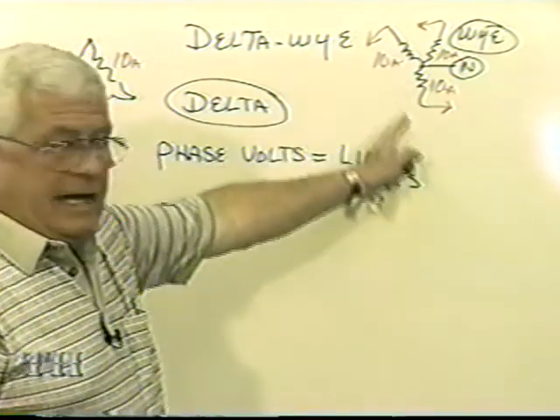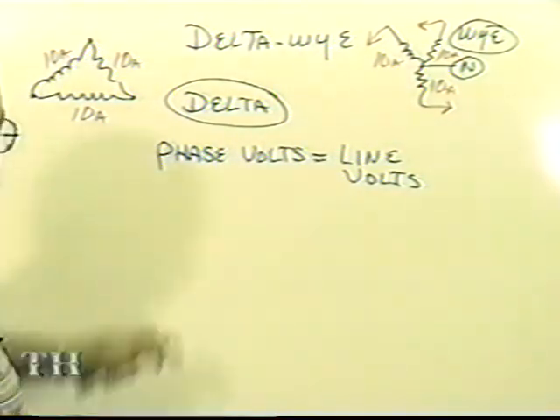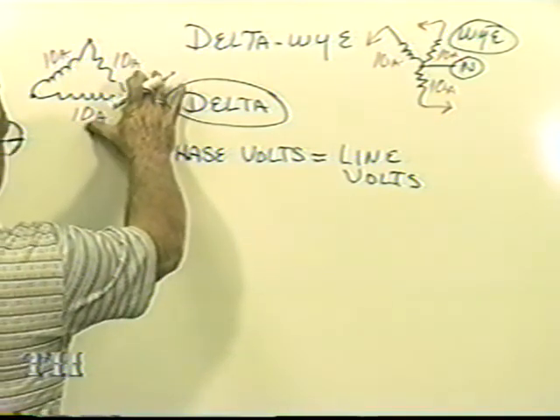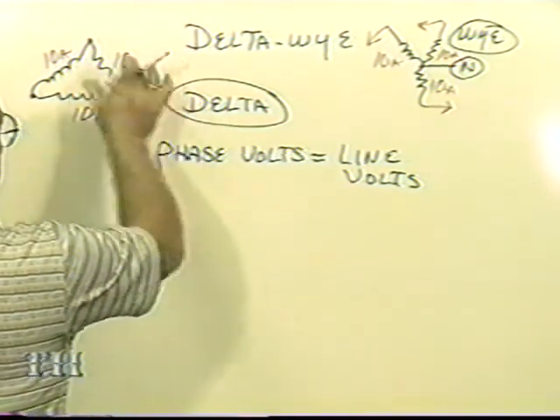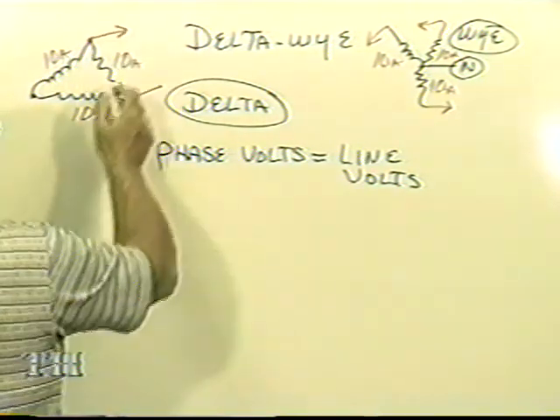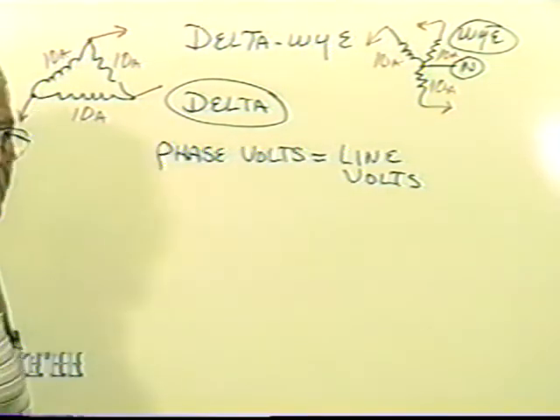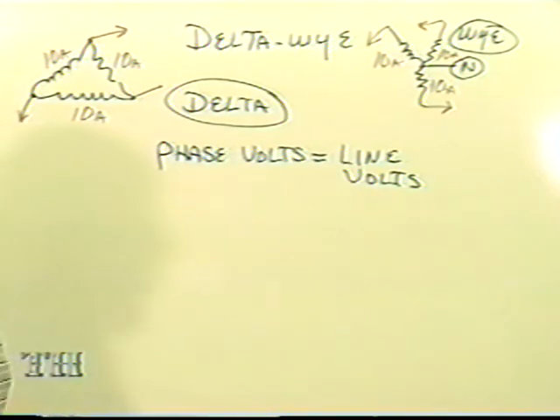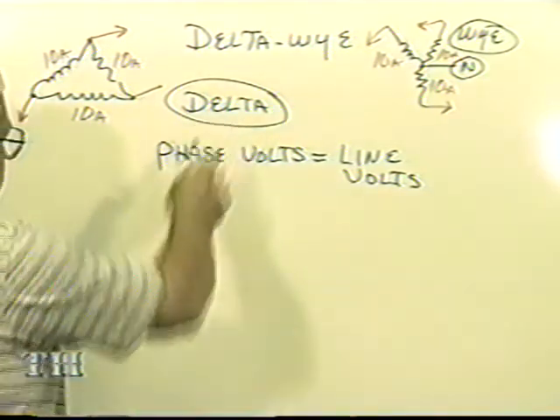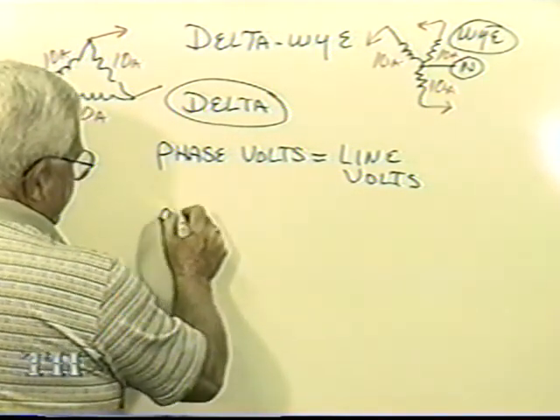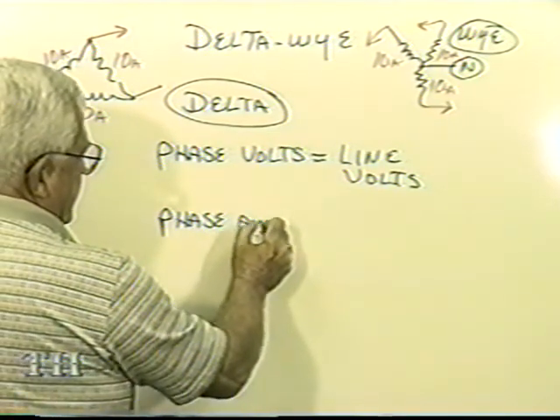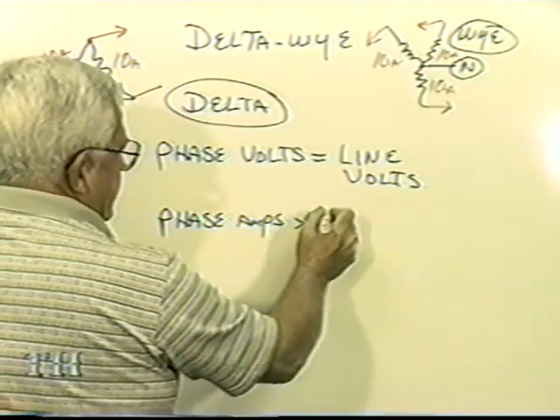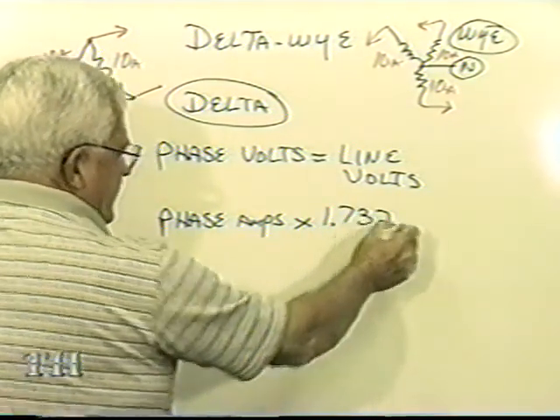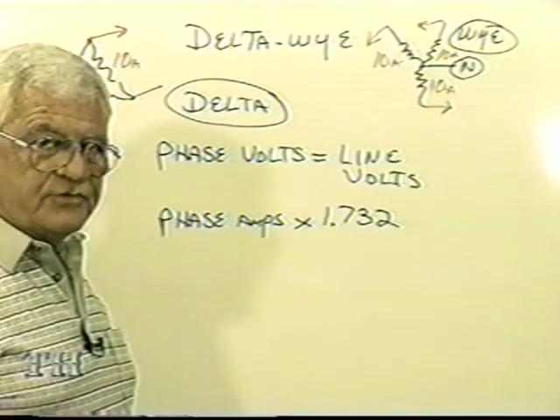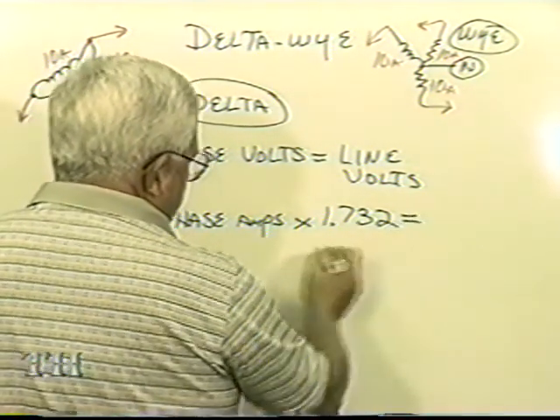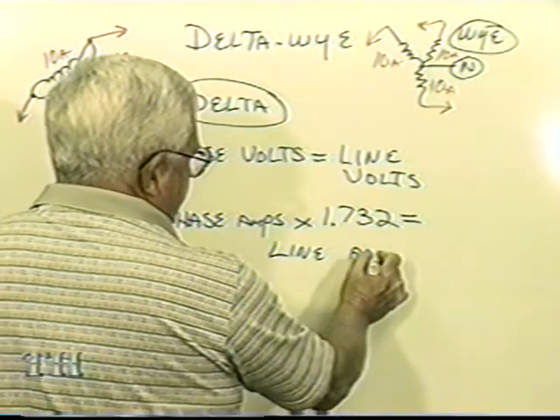You can see now in a Y how it went out. Well, can you see already what happens with a delta? With a delta now I have 2 coils, 1 line. 2 coils, 1 line. See, now it's not a straight flow. So what we do in this delta for current, you take the phase amps times the only number that I use, 1.732, the square root of 3. And this will give you line amps.